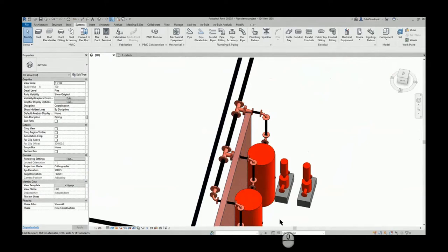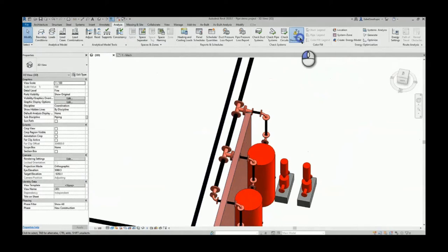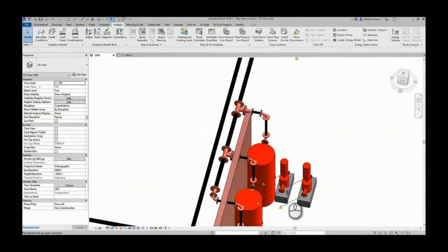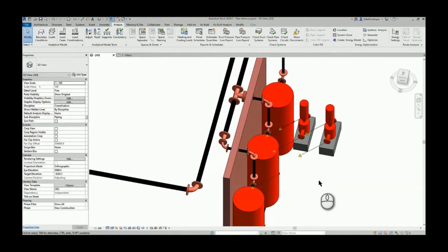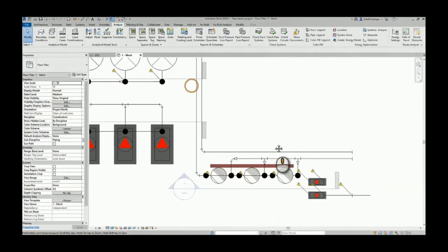There are other items in Revit to help you identify problematic areas within your piping systems. You can utilize the Analyze tab and the Show Disconnects button for pipes. This will show you all types of broken piping elements within your system. If you look out for warning signs, you can see any detachment or open ends within your pipe routing layout. It is as simple as connecting the pipe and closing off the system. This can be done in 3D and in 2D schematic.